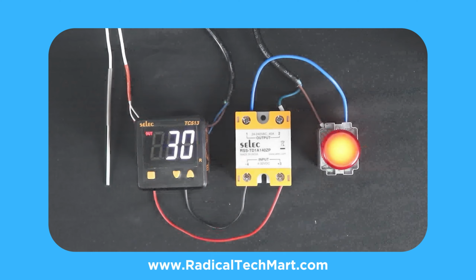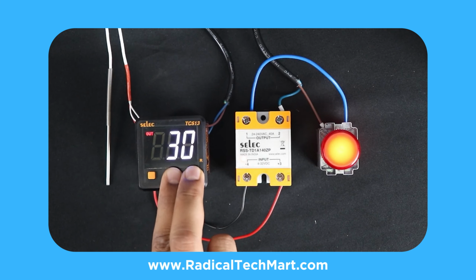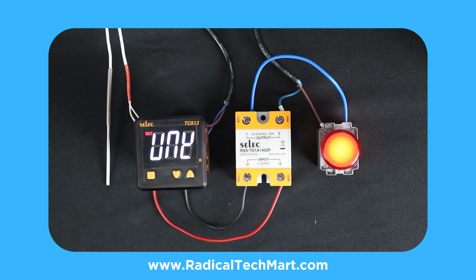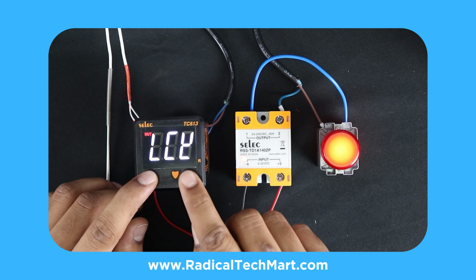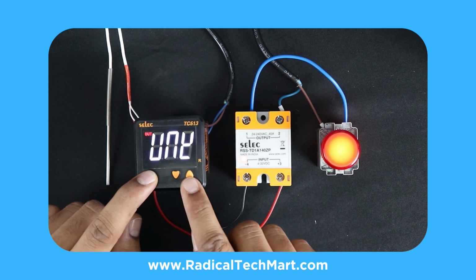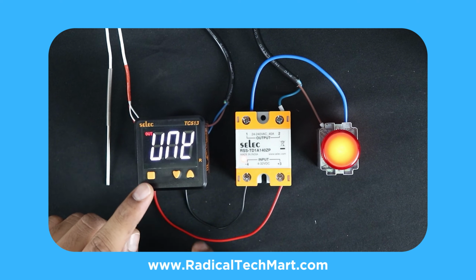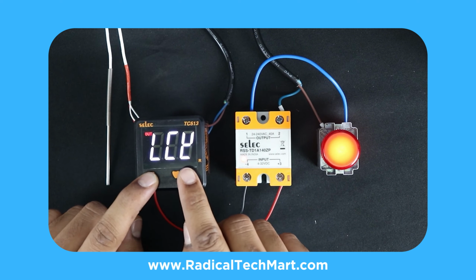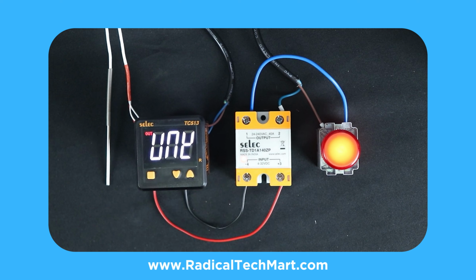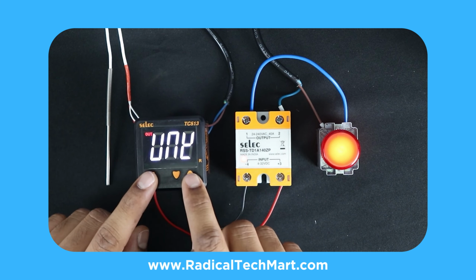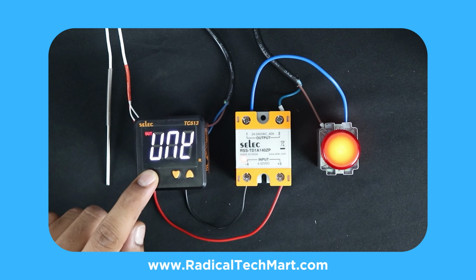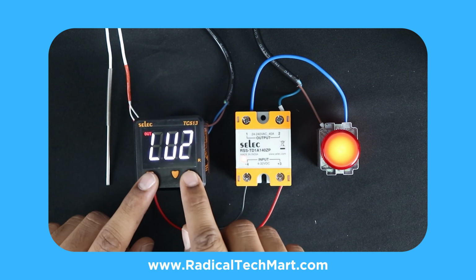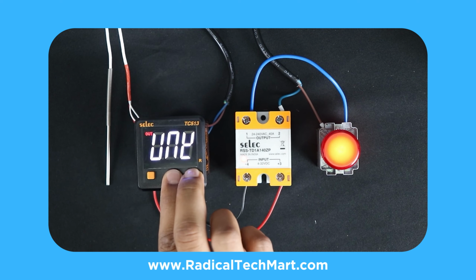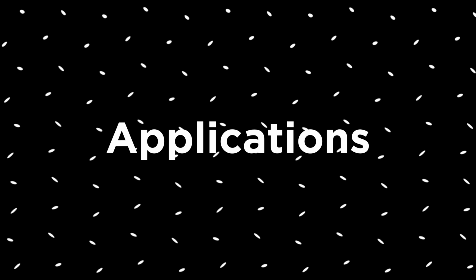To enter Level 3 programming, press the Instrument and Down arrow keys simultaneously for 3 seconds. Here, the unit shows the lock status along with the set point parameter. We can change the status to lock by long pressing the Set key and Instrument key once. Similarly, we can change the lock status of Level 1 and Level 2 using the same process. By using these parameters, we can create a lock to prevent unauthorized changes. To exit programming, press the Instrument and Down arrow keys for 3 seconds.